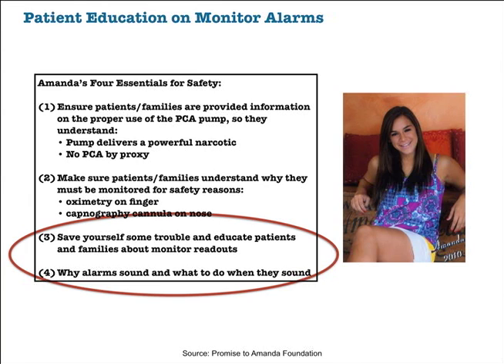The same goes for staff, who need to be re-educated on how to properly adjust those alarms, and not adjust them to a point where it doesn't alarm just because the patient isn't being cooperative. That can lead to trouble in the long run.